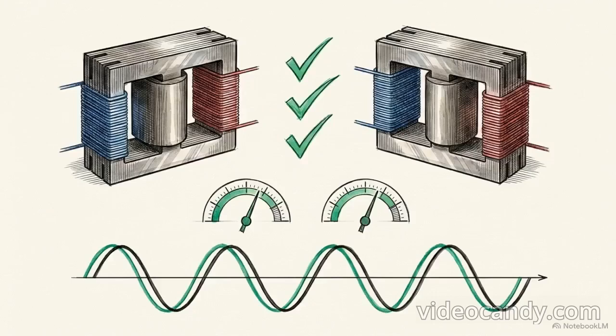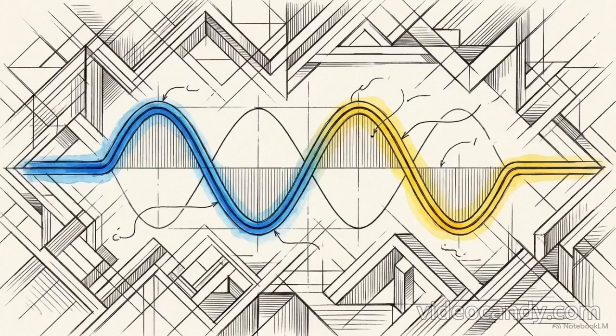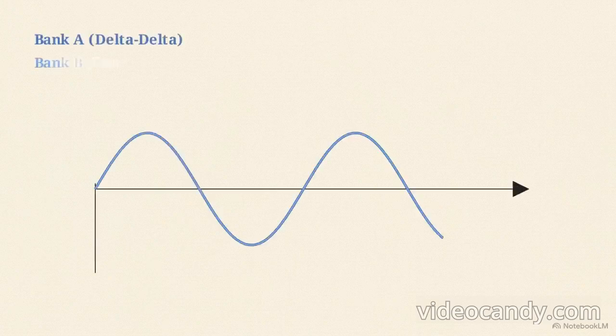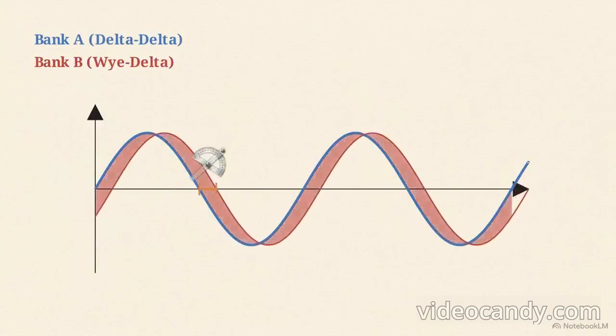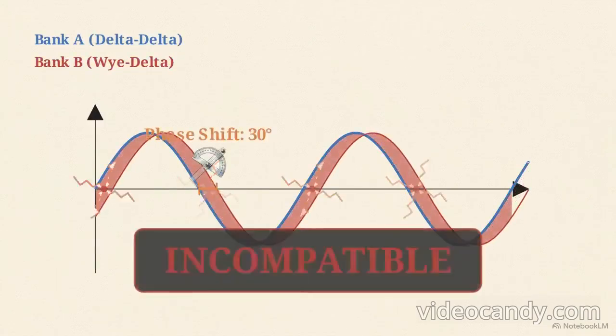As grid loads increase, a single transformer often isn't enough. Utilities must link multiple transformer banks in parallel to safely scale up capacity. Parallel operation requires strict uniformity. The transformers must have matching voltage ratios and identical per-unit impedances to ensure they share the load equally. But the absolute boundary condition is geometric. They must have zero relative phase displacement.